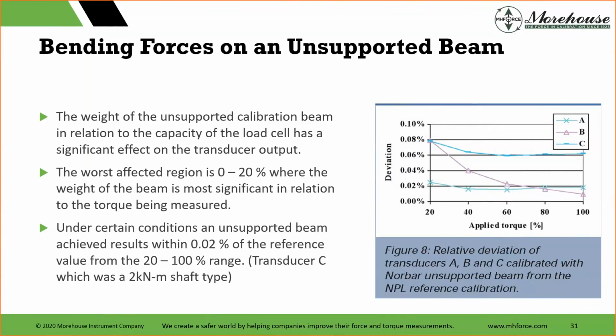Now I've taken this and summed it up to just tell people, hey, your beam matters, and it matters quite a lot. So if you're using a heavy beam, you probably have these errors, and you probably need several different beams, and you probably need to have that test to see, back and forth. That's what they did. They used the NPL machine as the reference, and then they put them in these. What this led to, and you could say, hey, Norbar and NPL, this led to Norbar redoing a lot of their beams and making them lighter. So they're better than this now. But if you have the older beams and stuff like that, you could still have this.